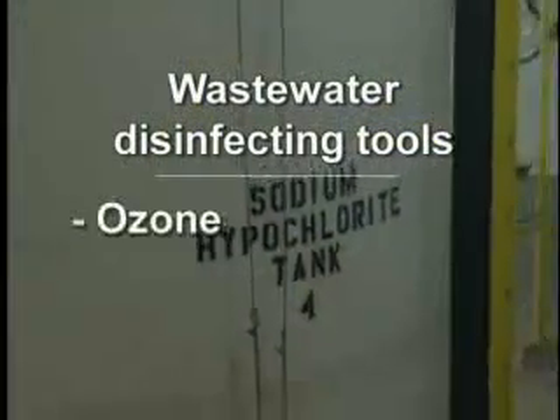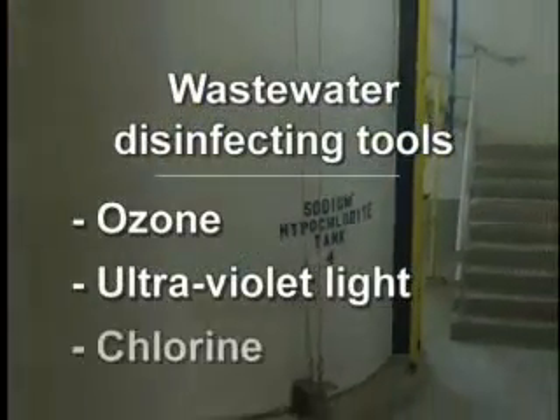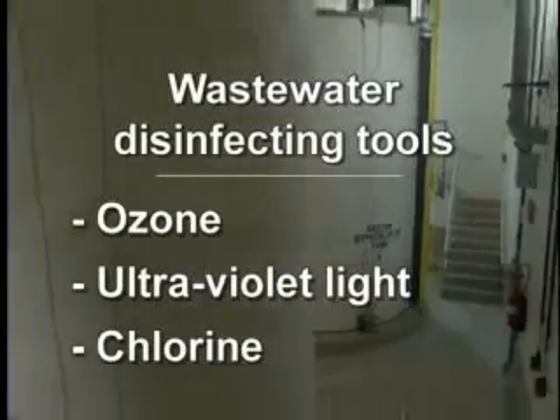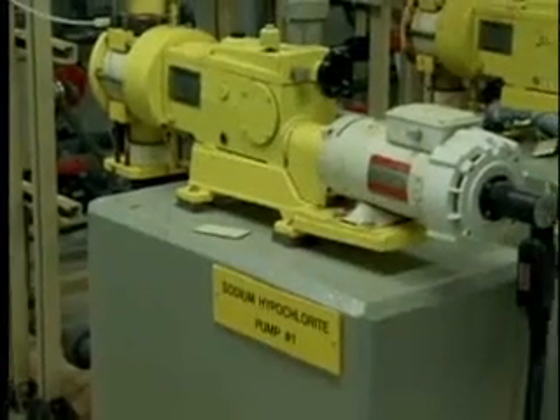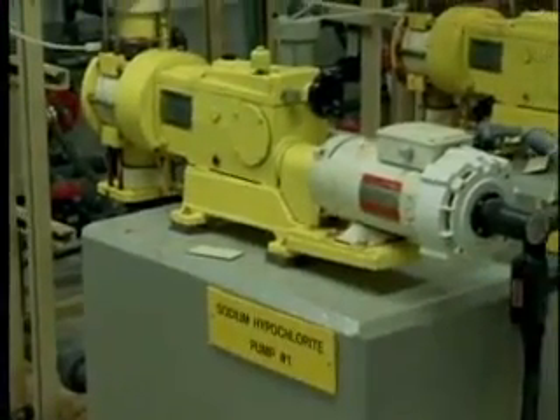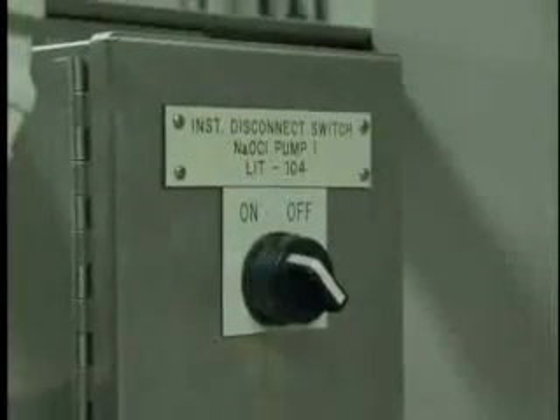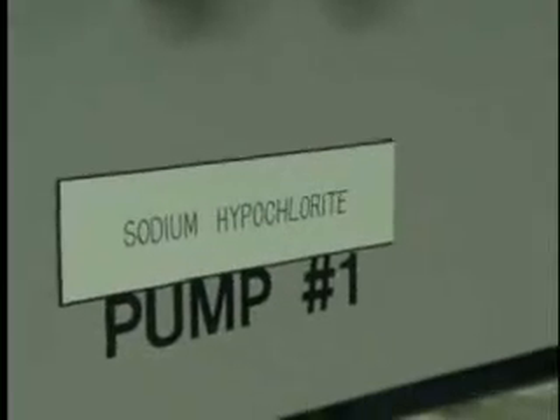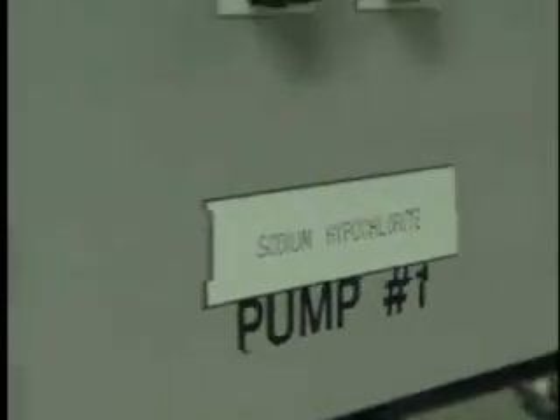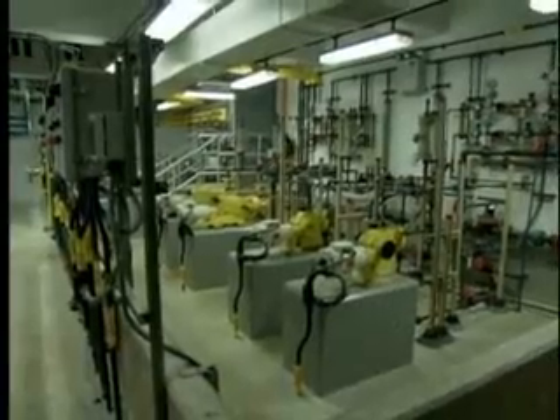You can disinfect wastewater with ozone, ultraviolet light, or chlorine, and that's what we use, a type of chlorine. We use sodium hypochlorite, which is a real strong bleach, about 12 to 15% chlorine. So these are the metering pumps that deliver that chemical to the wastewater flow for disinfection.